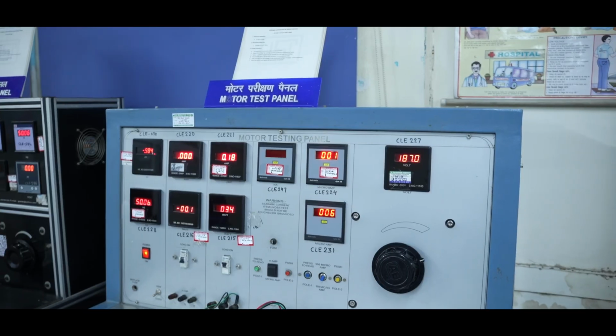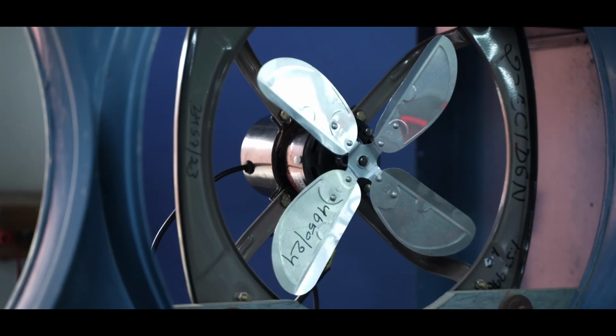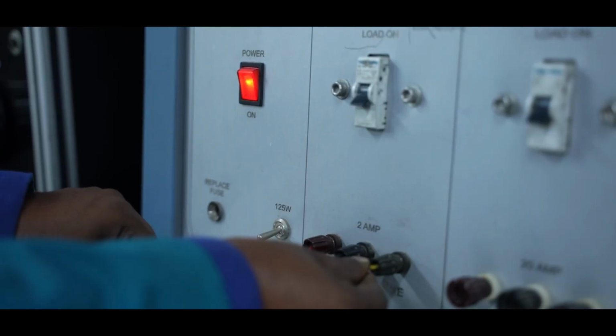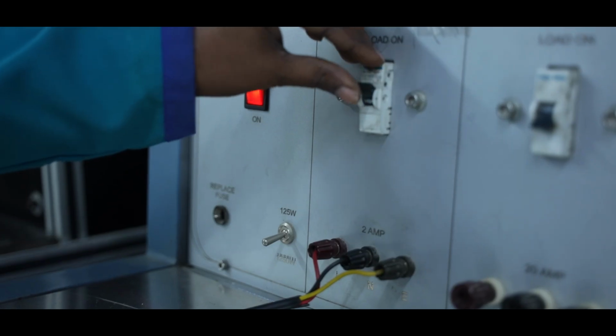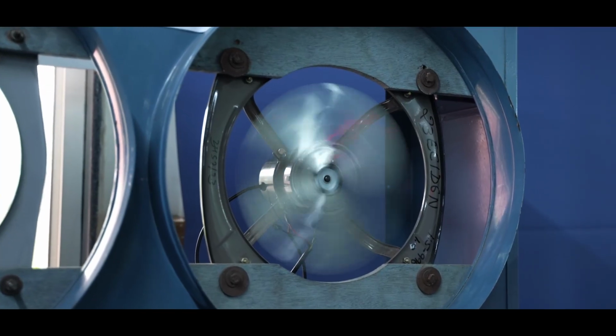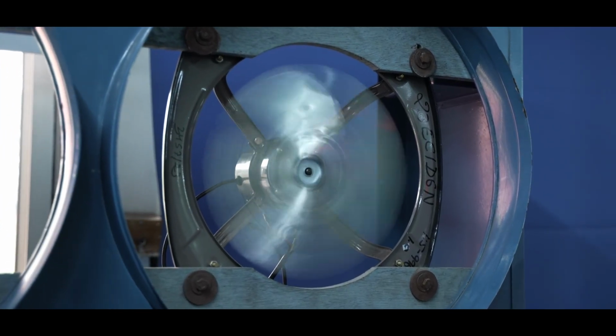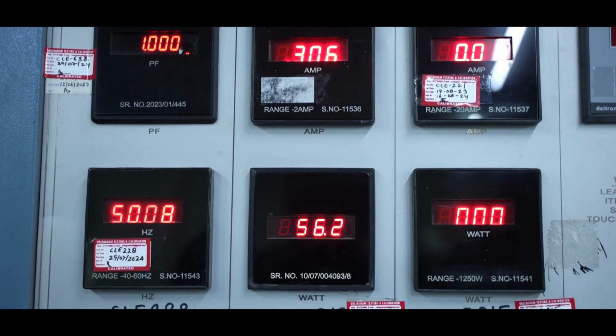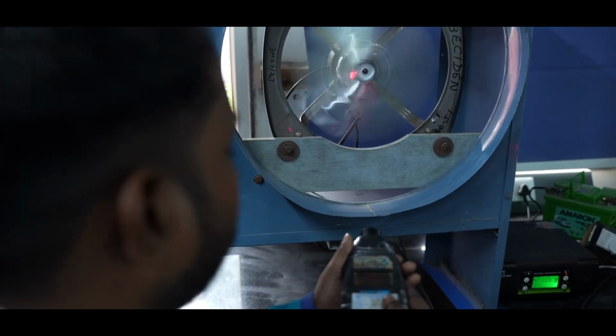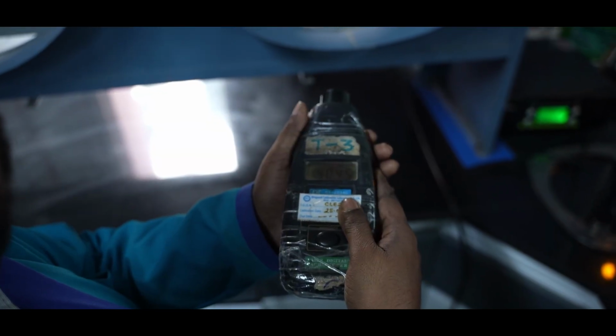Full load performance test, Clause 12.5.1. Testing under full load provides details about the motor's efficiency, power factor, and operational stability. In this test, the motor is subjected to load using the blades of the motor. Parameters like voltage, current, torque, and speed are carefully monitored to assess overall performance.